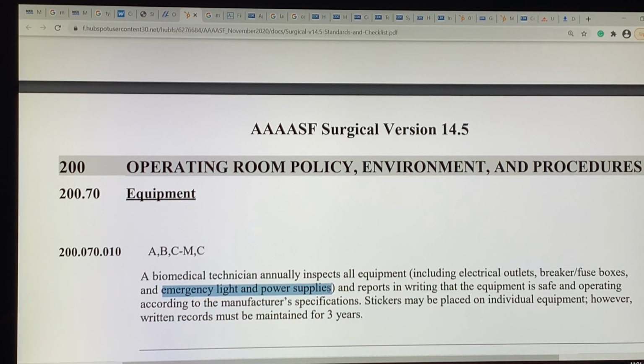Those batteries go often, so sometimes they come with your alarm system. If you buy a regular alarm system, they would work with the alarm system. I do believe you need one wired to the emergency power for the event that there would be loss of power in the middle of a procedure. There would be enough to cauterize, close, and get out with the light that's available.